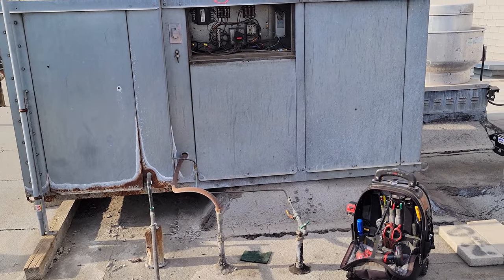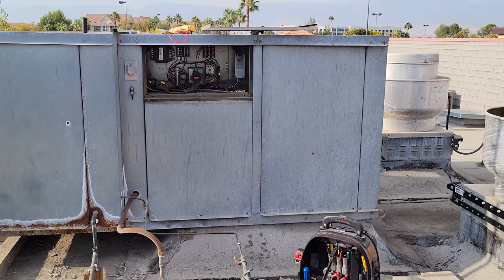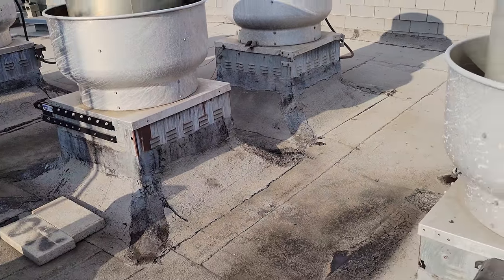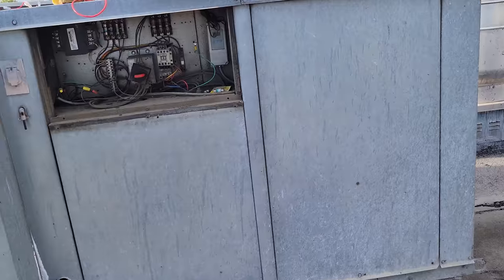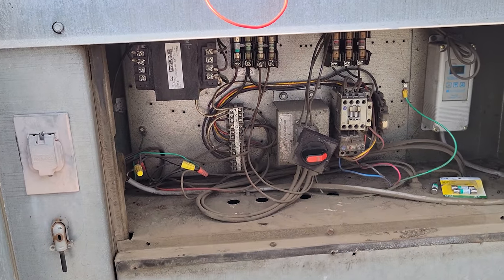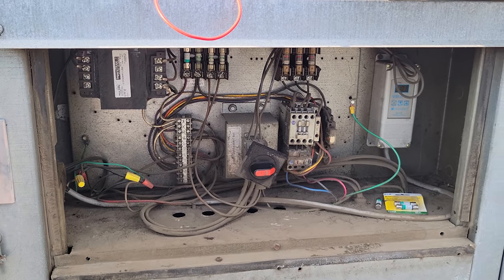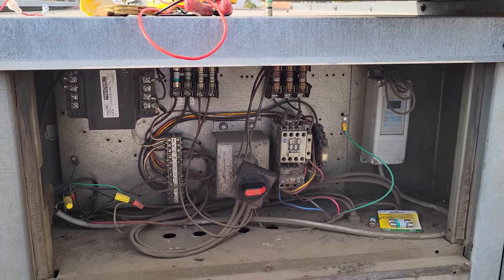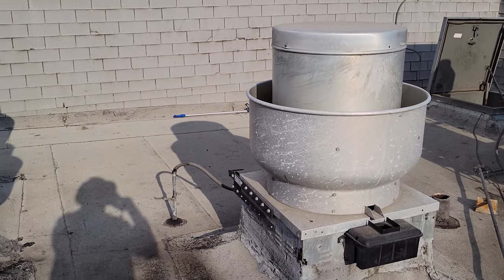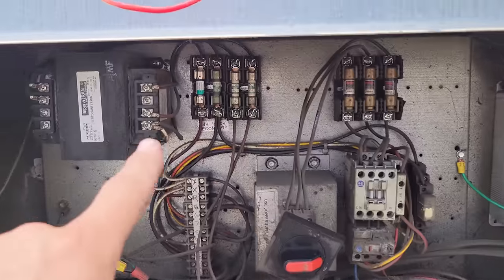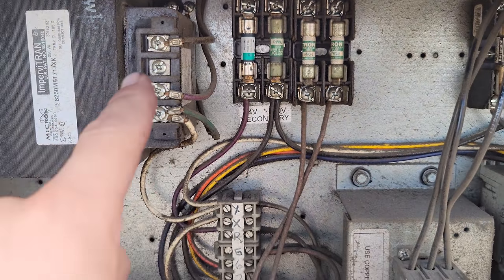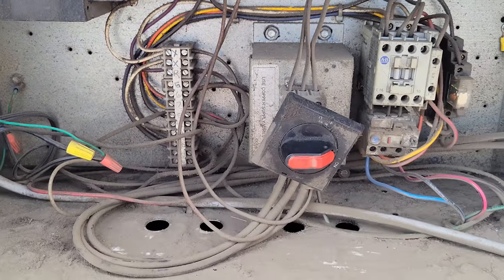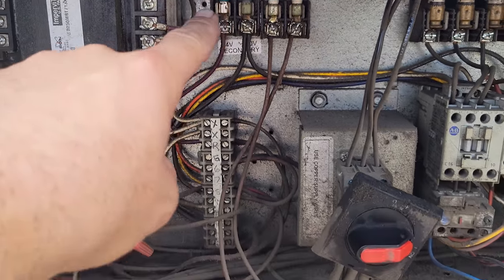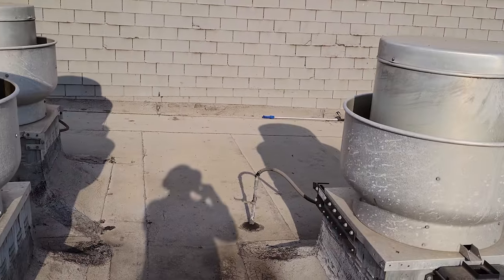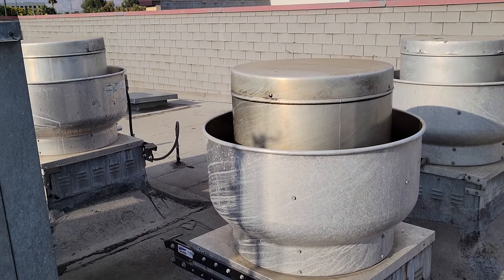Originally, when they called me, I thought all their refrigeration equipment and their ACs were down too, so that's why I was thinking they lost a phase. But when I got here, they're like, no, it's just our exhaust fans. So what's happening is the exhaust fans have an interlink in here, and the cooking equipment will not turn on if the exhaust fans are not running. So if the hood switch is not on, where the main power switch is, the cooking appliances can't turn on. Now, it'd be one thing if they just had one exhaust fan that went down, but because all of them were down, because the control voltage, the 24 volts, which comes from that transformer through the fuse into here and then goes down to the main power switch, because that fuse blew, the hoods could not turn on the motor starters for the exhaust fans, and all the cooking equipment is interlinked into those motor starters.